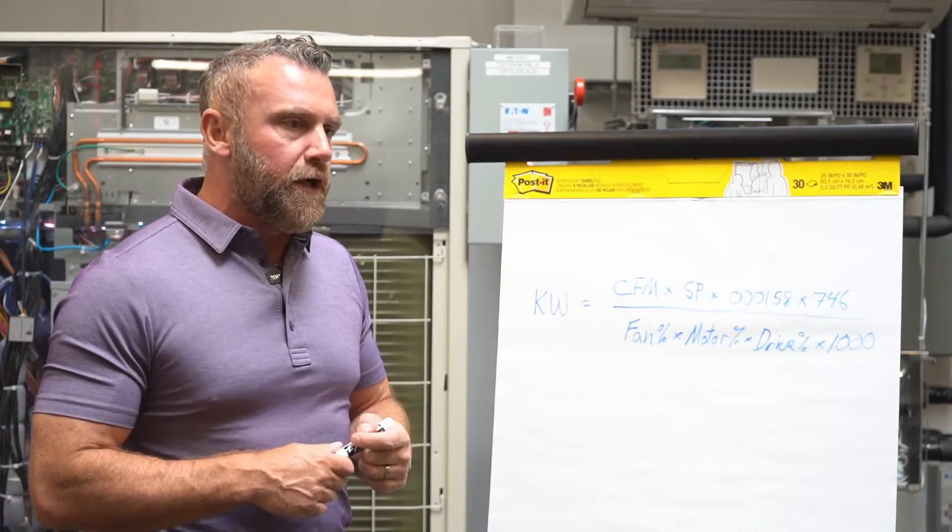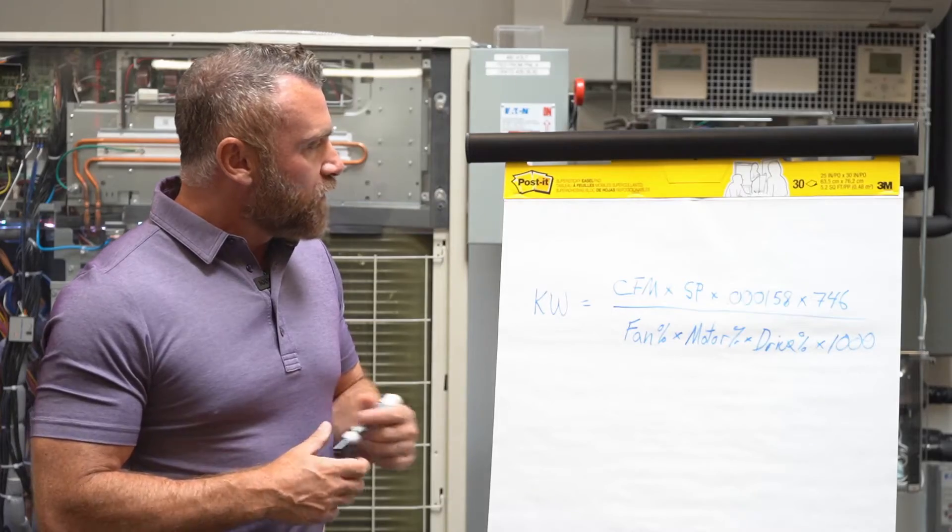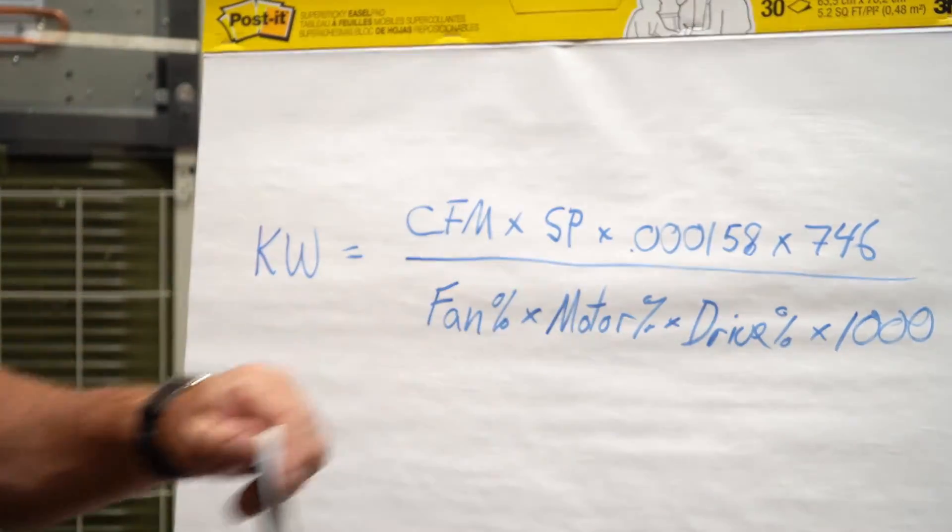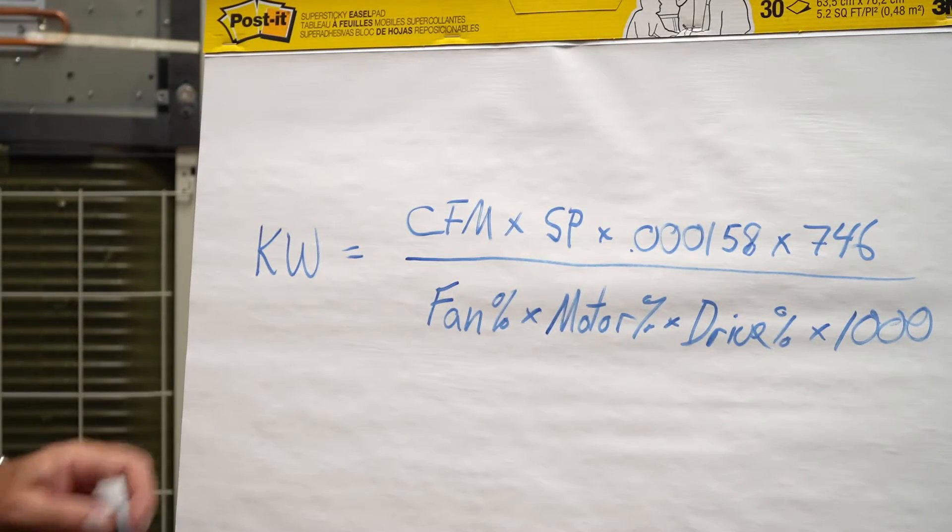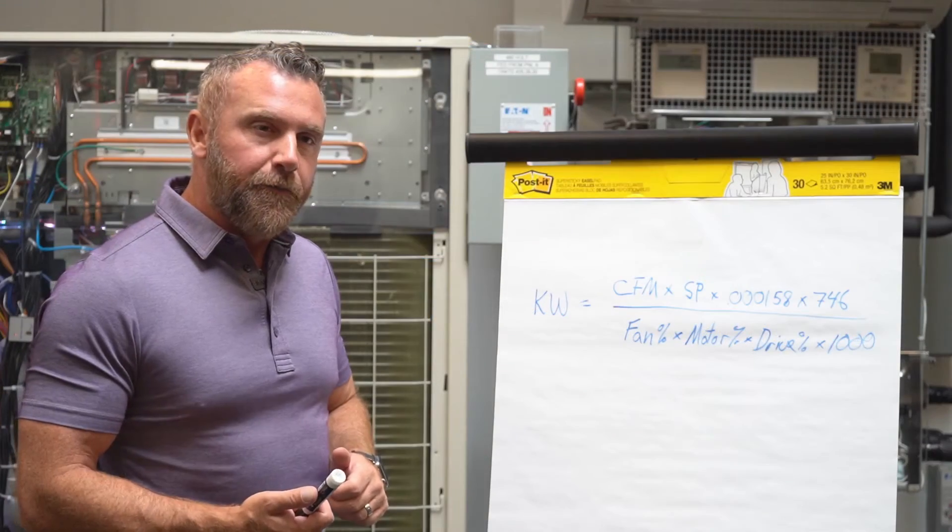So all of that gives us KW, and if we want to give electrical engineer a horsepower, all we have to do is factor out this 746 over 1,000, so it becomes 0.746, divide KW by that, and that gives us horsepower.